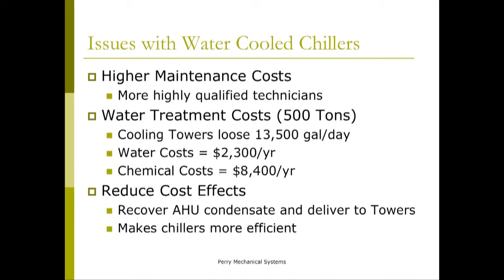And the added benefit of doing that is the water they're putting back in the tower is colder, so the chiller is going to run more efficiently. And it's cleaner as well, so it's going to need less water treatment. So the other items associated with that are your water treatment costs, your water costs, and your chemical costs. This was based on McAllen water rates. So you're looking at almost $11,000 a year in additional cost on a 500-ton water-cooled machine of maintenance of just the water side.